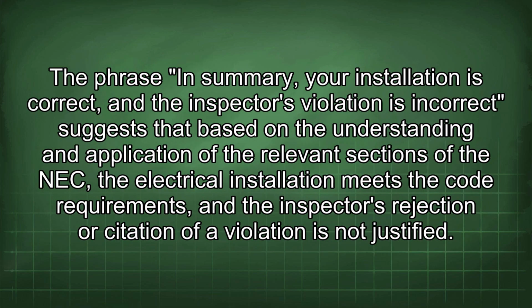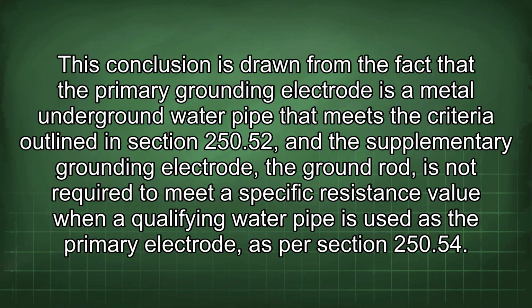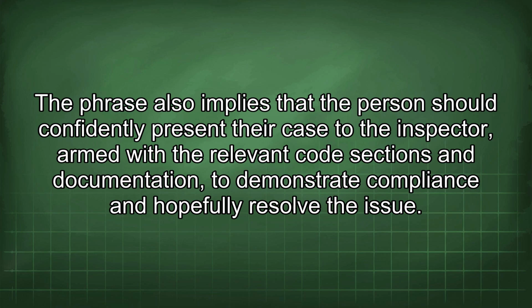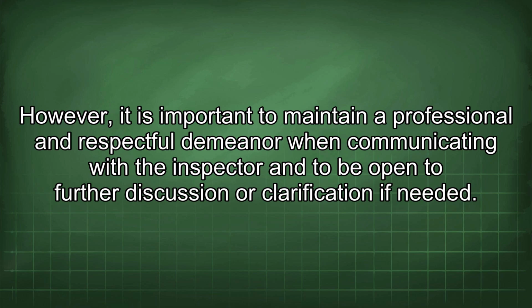The phrase in summary, "Your installation is correct," and the inspector's violation is incorrect, suggests that based on the understanding and application of the relevant sections of the NEC, the electrical installation meets the code requirements, and the inspector's rejection or citation of a violation is not justified. This conclusion is drawn from the fact that the primary grounding electrode is a metal underground water pipe that meets the criteria outlined in section 250.52, and the supplementary grounding electrode, the ground rod, is not required to meet a specific resistance value when a qualifying water pipe is used as the primary electrode, as per section 250.54. The phrase also implies that the person should confidently present their case to the inspector, armed with the relevant code sections and documentation to demonstrate compliance and hopefully resolve the issue. However, it is important to maintain a professional and respectful demeanor when communicating with the inspector and to be open to further discussion or clarification if needed.